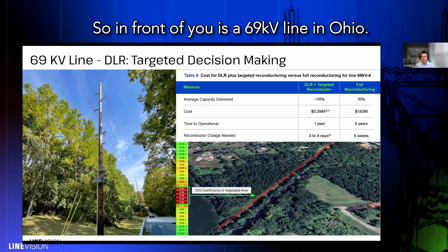The trees block the wind, and our static line rating assumption for this line is 2 meters per second for wind speed. That doesn't hold here in this highly vegetated corridor, so we actually have lower capacity than we thought we did in this area.